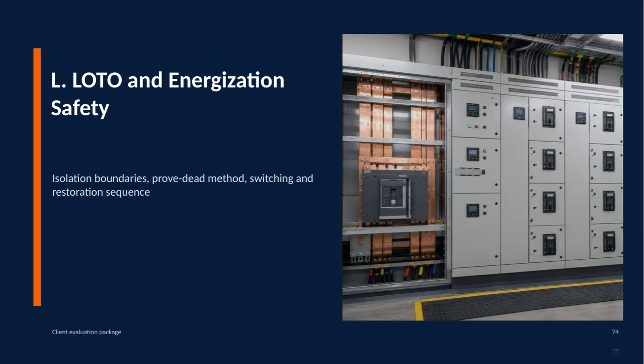On this slide, we focus on LOTO and energization safety, which is critical for preventing accidents during maintenance. Key concepts include defining clear isolation boundaries to ensure that energy sources are properly controlled. The prove-dead method is an essential step where you verify that all energy has been safely disconnected. We also cover the correct switching and restoration sequence to avoid unintended energization. Finally, there's the client evaluation package, which helps assess compliance and understanding of these safety procedures. These elements together create a comprehensive approach to keeping everyone safe.